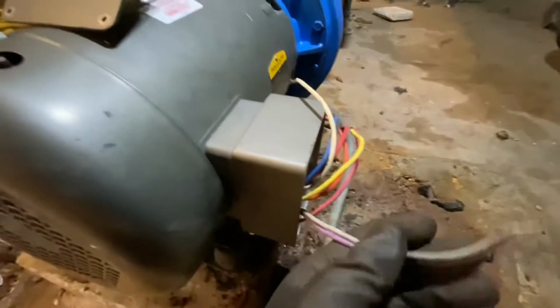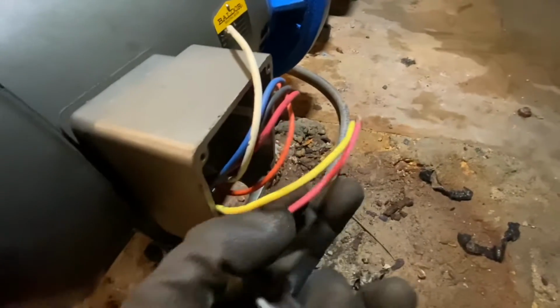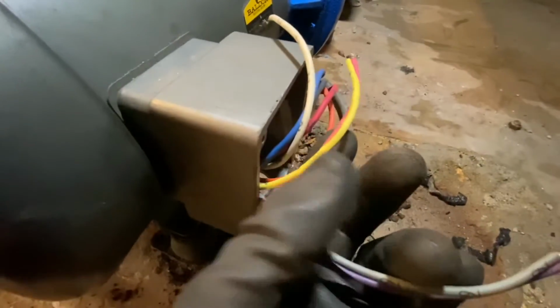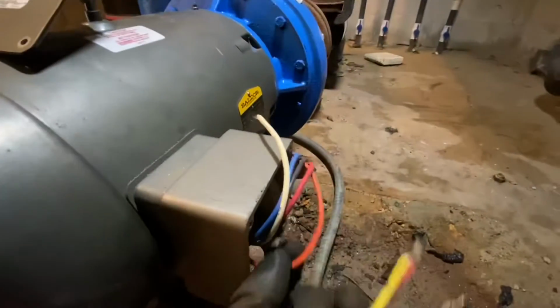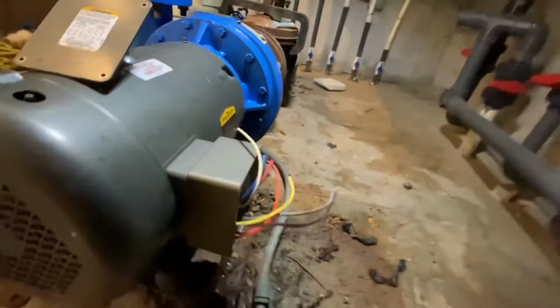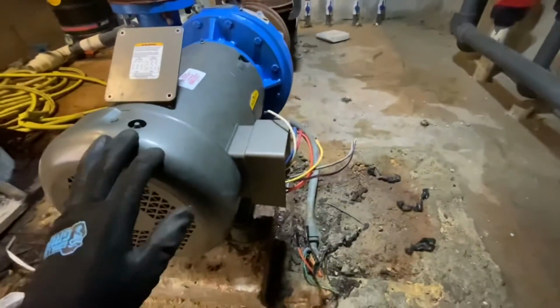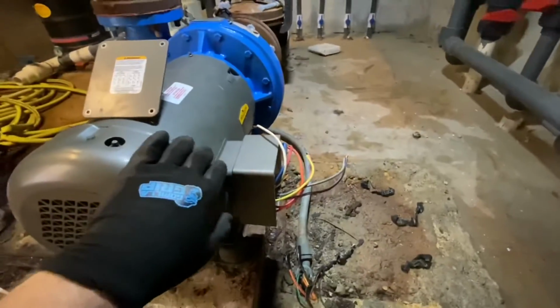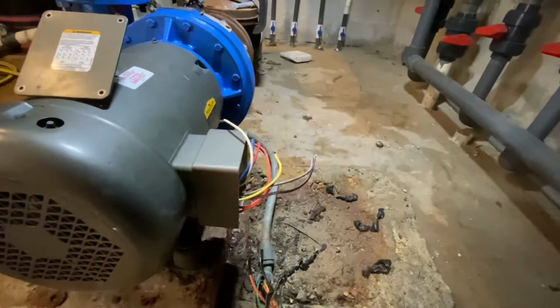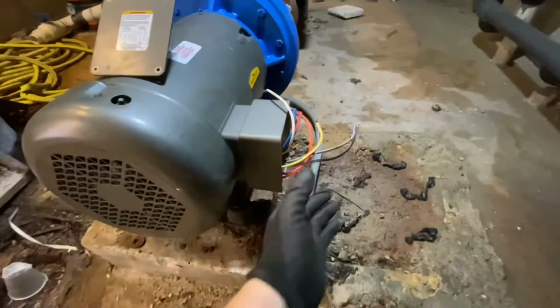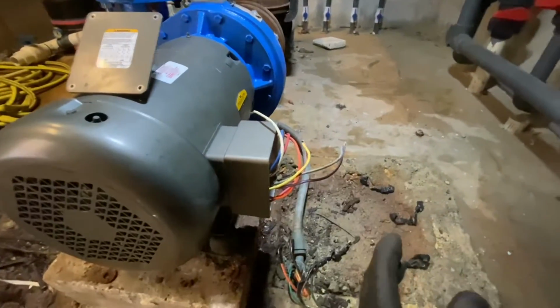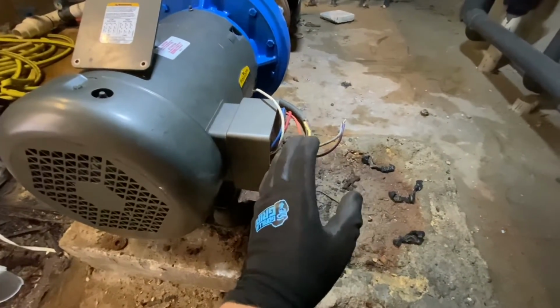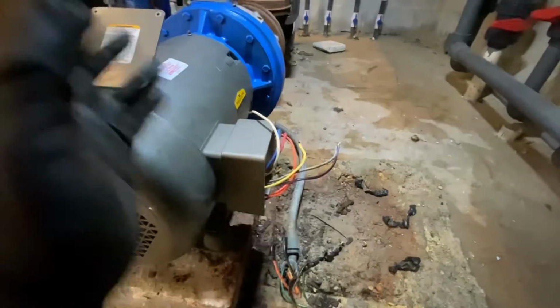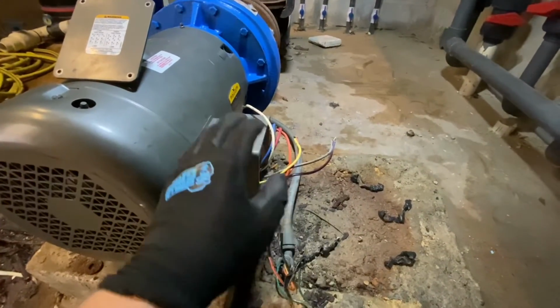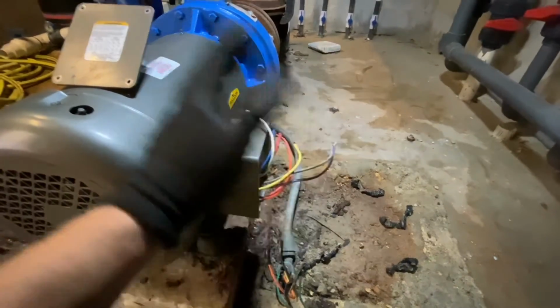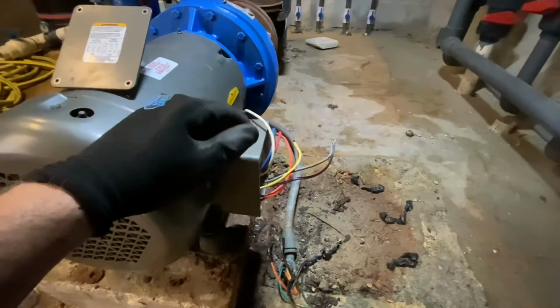So usually, this motor's already pre-wired for 480. 7 and 4, 7 and 4. And the reason why they do that is because if you're a tech and you don't know, right? If you have this motor wired for 208, 230 and you apply 480 on it, most likely you're going to fry it, all right? So it comes ready for 480 for the higher voltage. So if you put your high voltage on this motor, it's just going to run, you know? So you have to change it to the low voltage if that's what you're using.